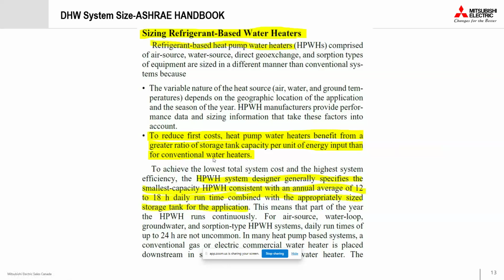Especially if you have a single refrigerant-based domestic hot water heater, to reduce the first cost you would like to have the smallest size of heat pump, which benefits from a greater ratio of storage tank capacity per unit of energy input, as compared to a conventional water heater. In that case, your hot water heat pump system designer generally uses the smallest capacity possible, consistent with an annual average running time of 12 to 18 hours or maybe more for that system. So you will have high storage and low capacity, and that low capacity system will be running for a longer period of time as compared to the 30-minute or 3-hour demand.